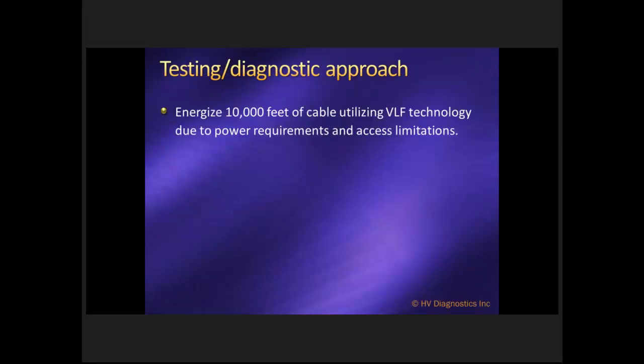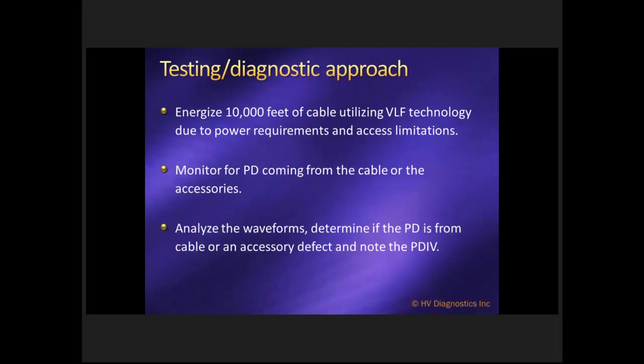So the testing diagnostic approach: we would energize 10,000 feet of cable, which is obviously a very long length of cable. We couldn't go much longer than that due to power requirements and also access limitations. We had no real access other than about 10,000 feet. There were no junction boxes, for example. We had to monitor the PD coming from the cable or the accessories, and if there was PD, we needed to analyze the waveform so we can detect whether it was inside the cable, which was more of a warranty issue, or inside the accessory, which fell on a different responsibility area. Any PD detected inside the cable was considered to be unacceptable. That was just the agreement we came up with on the supply of the cable.